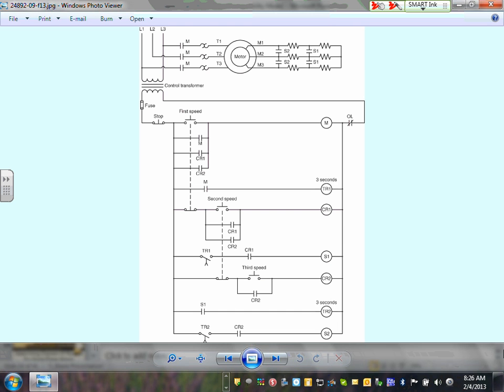Can I use this one in an air handling unit? Yes. Is it a good application? No. For machines, we don't even specify the motor on the machine. It comes from the manufacturer. Just be aware of it. I've never been in a place where I have to specify a wound rotor motor. It usually becomes part of the machine. But be aware that there is something called a wound rotor motor, and that's how they work.